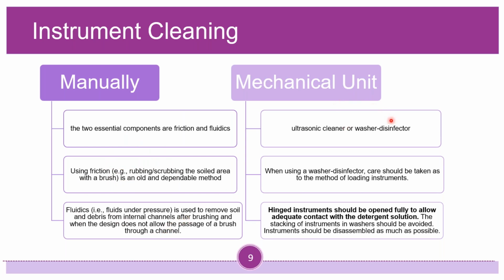Next is mechanical units. So these are going to be your ultrasonic cleaners or your washer disinfectors. And this is where your equipment and instruments are going to go once you're done with the actual manual cleaning. When using a washer disinfector, care should be taken as to the method of loading instruments.